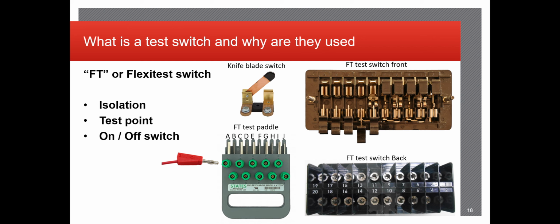So those test switches for the current circuits are utilized because at the bottom there are shorting blocks, meaning that if one of those gets opened accidentally and the circuit is still somehow hot and has current running on it, the block will cause a short and bring it directly to ground, and it may operate the breaker in this case, but it won't blow up the CT because the current circuit will still be completed. It'll just run directly to ground. So extremely useful, very much safer to utilize those rather than running them directly into the relay, for example, and a good tool to remember.